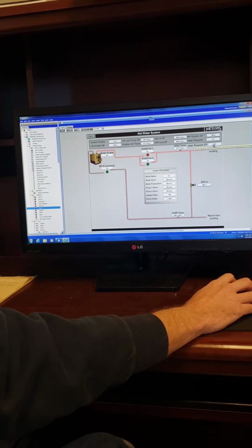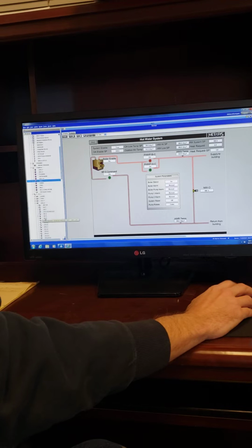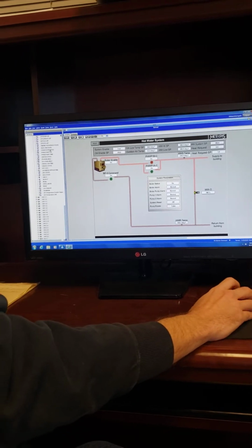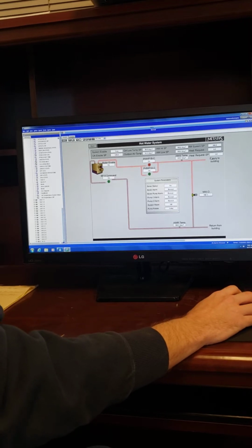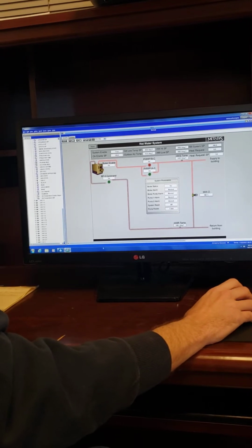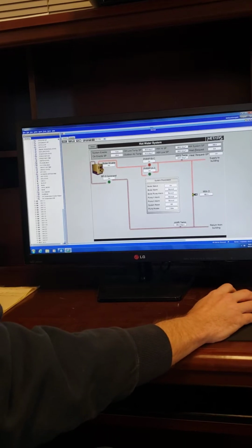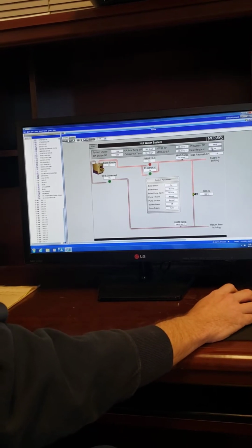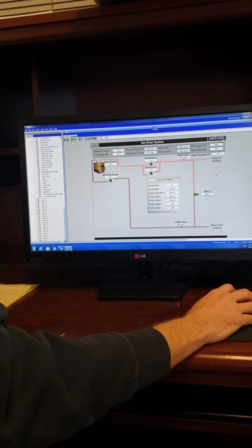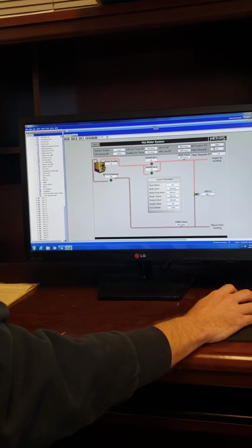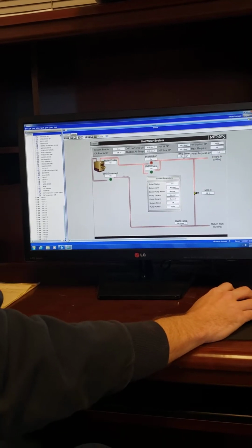This was originally set for 10 zones requiring heat, so you have almost half of your building, a little under half, freezing before it'll ever kick on your boiler. And then you're kind of fighting against it. So if you ever come in and your boiler's off and the building's cold, you want to check this heat request and make sure that it is above this heat request set point. So how do you determine the heat request, that 8? Yes, that 8. As long as that's greater than this 3, that should have your boiler system on.